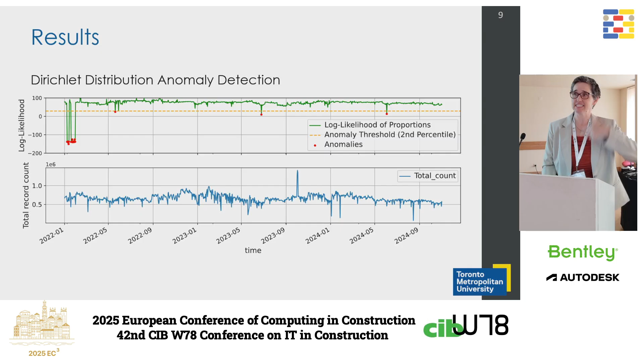But what's really interesting, if you look at the cluster of points at the far left, you can see it's very, very unlikely that we would have that. But if you look at that data stream, at the sheer number of points, you would have no way of knowing that that's actually wrong. When we looked at the data, and I'll show you what this shows in the next piece, you can see our main central air handling system actually stopped reporting entirely. We had a period of several days where we had no data from that one system. But in context, we have 14,000 points. We never figured out that we were missing that because there's only 22 points on that, and some of them are simple day-night occupancy shifts.